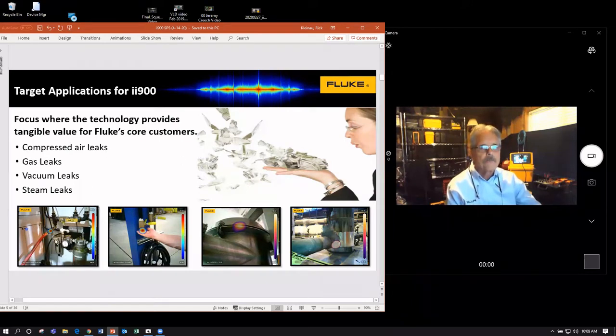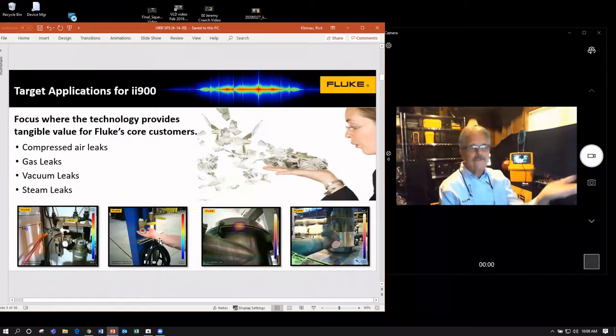If you look at the first picture below, there's an air leak, but also gas leaks. I like this picture where you can see the guy's hand. You see it looks like he's holding the little red spot. That's the leak. That's an argon gas leak. And the man whose hand is in the picture looked at me and he said, "This is gold dripping on the floor." These folks did a lot of welding. The argon gas is used for welding. If you notice, there's nothing hooked up. Somebody just failed to tightly close that valve. It's amazing how many times you see just carelessness closing off a compressed air valve or a gas valve like that.